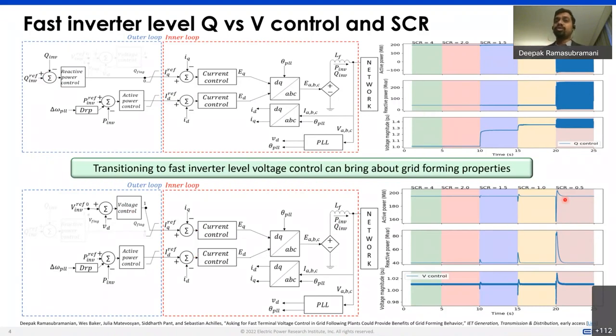Now, this is not to say that every PLL-based system will be stable in these conditions. Control tuning, control design does play a crucial role, but what it is to say is that by having a PLL also, you can derive and bring about the stability, which throws light on the importance of having this level of voltage control on the inverter level side rather than having Q control. And then that becomes a distinguishing factor for grid forming property or for grid forming performance.